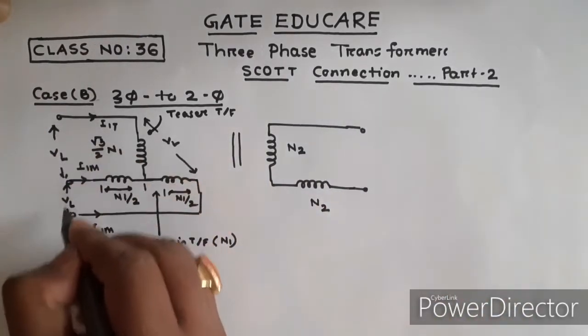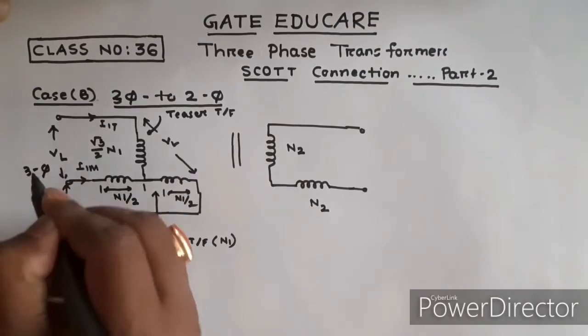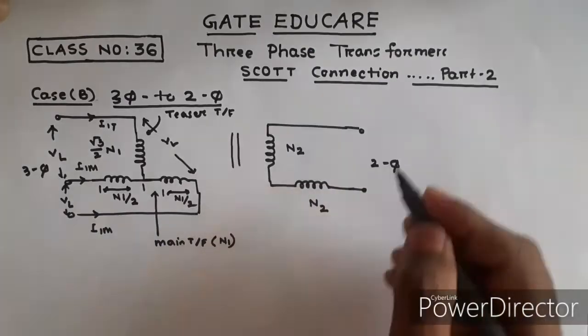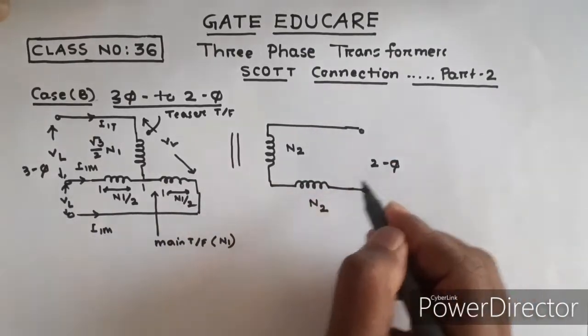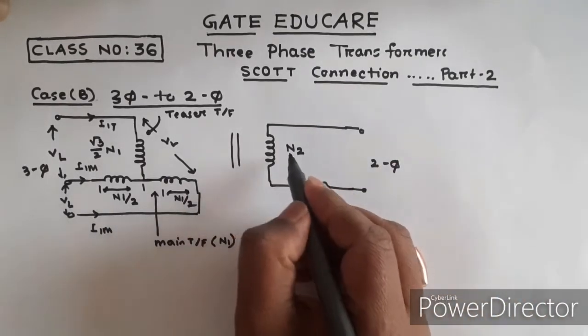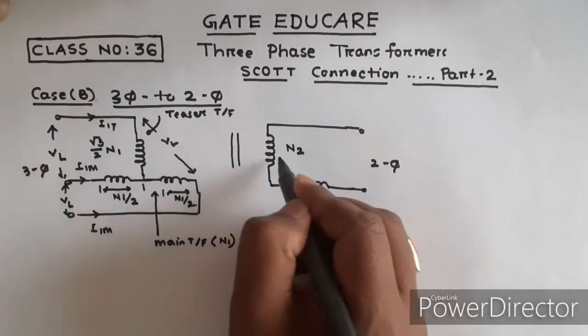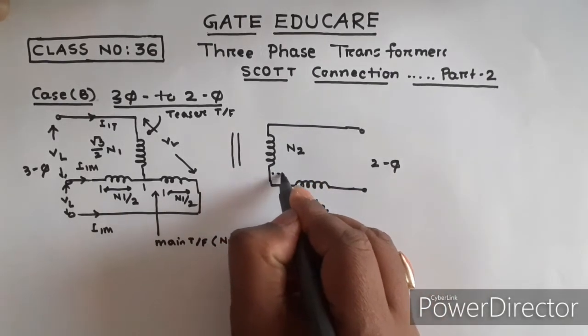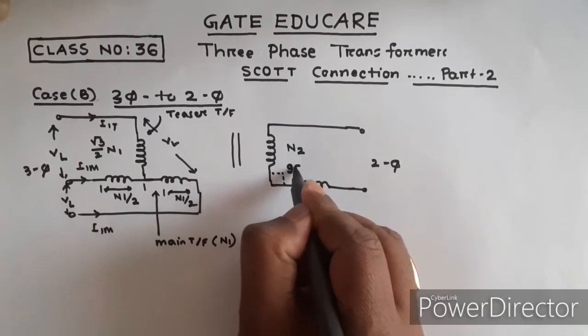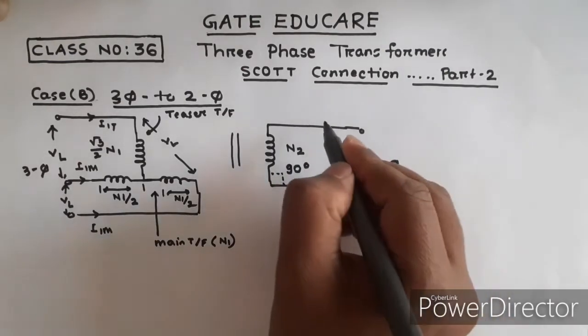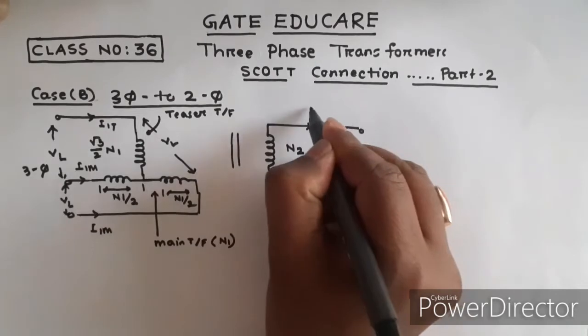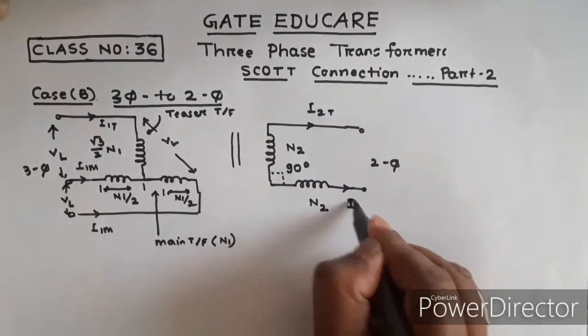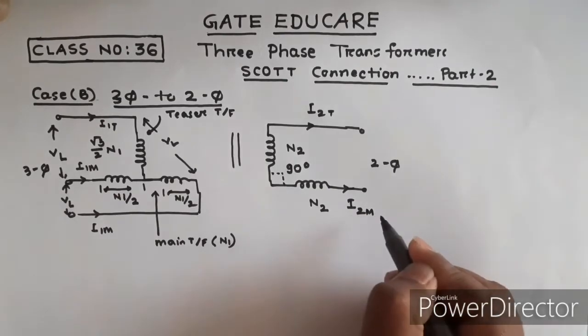For a three-phase to two-phase conversion to produce a balanced two-phase output, the number of turns of the secondary of the main transformer and the teaser transformer must be the same. The phase displacement between the two secondary outputs should be 90 degrees. The teaser secondary current is I2T and the main transformer secondary current is I2M.